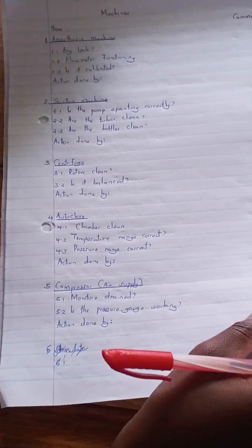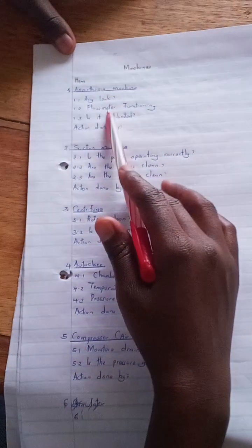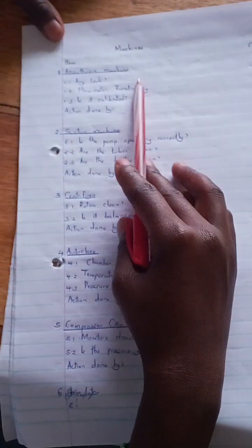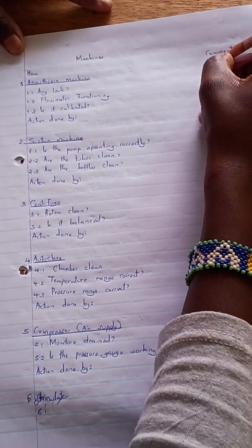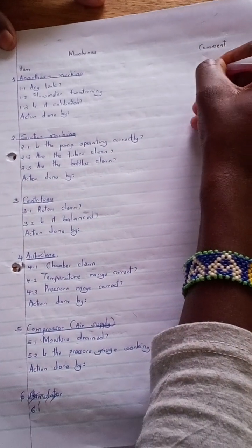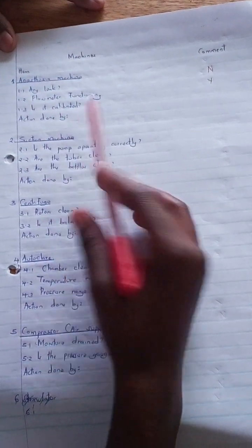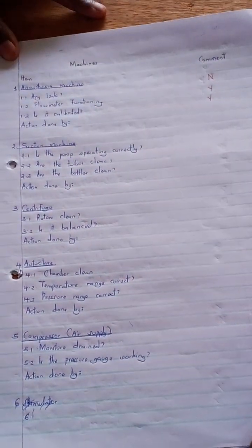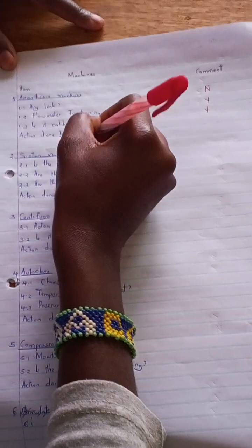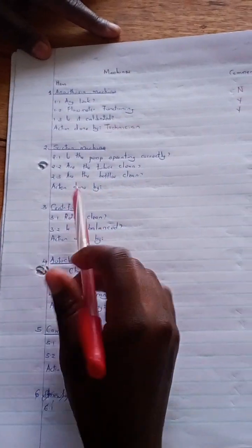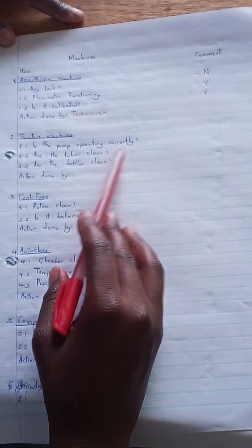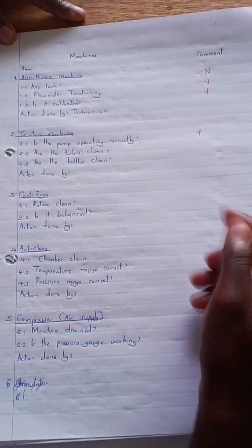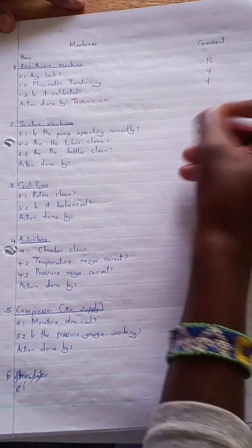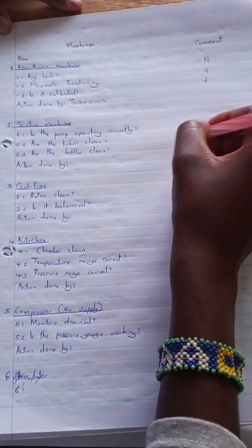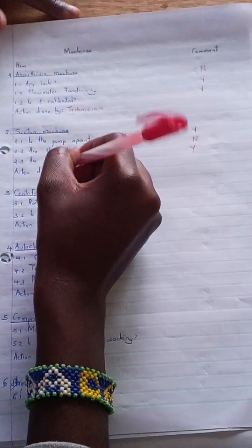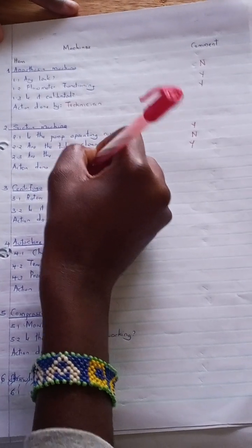Then we go to machines. We are done with equipment. The machines. The anesthesia machine. Is there any leak in the anesthesia machine? No. Flow meter functioning? Yes. Is it calibrated? Yes, it's calibrated. The action is done by a technician. Let's go to machine number 2. That's the suction machine. Is the pump operating correctly? Yes. Are the tubes clean? When they are not clean, we place no. Are the bottles clean? Yes. The action is done by intern, student.